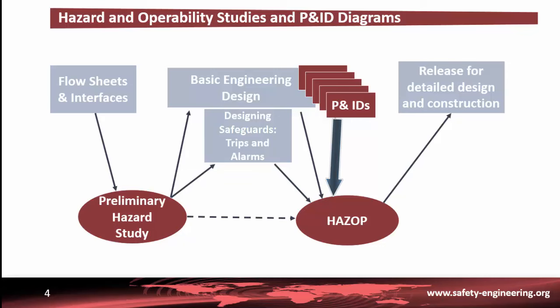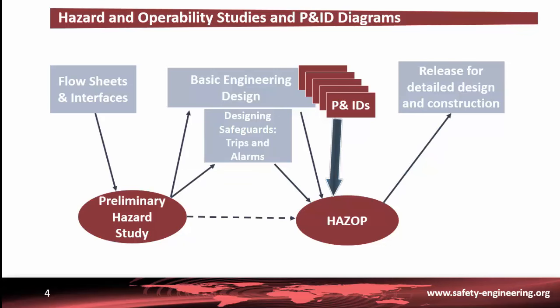For instance, such a diagram is used when a HAZOP is conducted to check and investigate the design of all facilities in order to identify any potential hazards and operability problems which could arise, particularly through deviations from the design intent. A set of lists of required actions and recommendations to improve and mitigate the consequences of the problems identified or hazards will be recorded and presented in the form of a HAZOP report. The HAZOP review is based on the PFD, P&ID and other project documents.